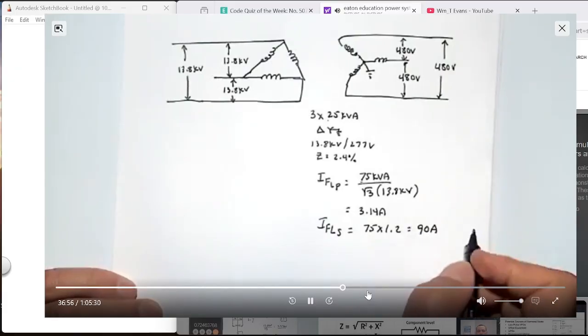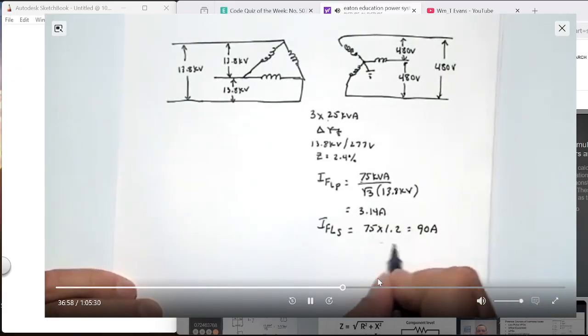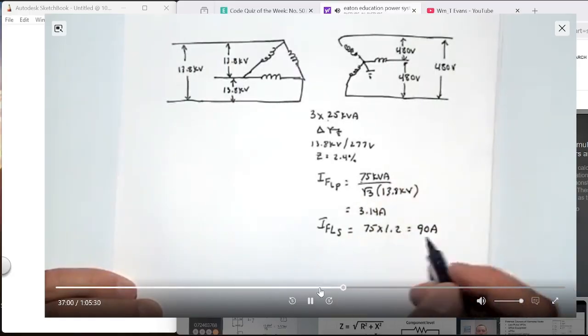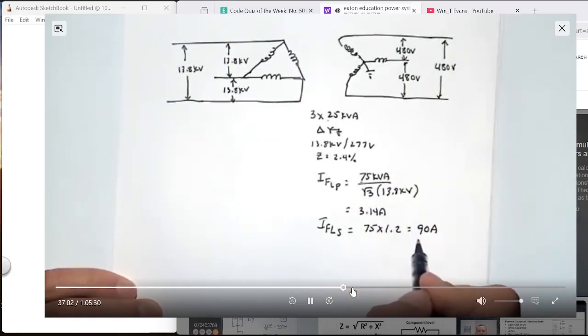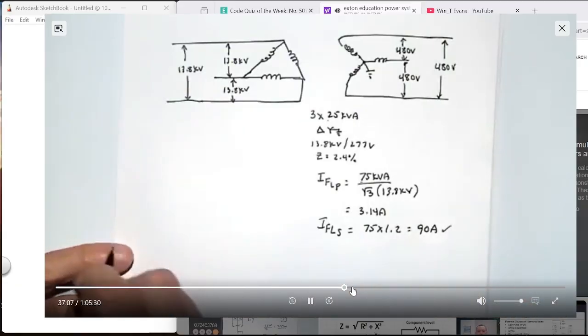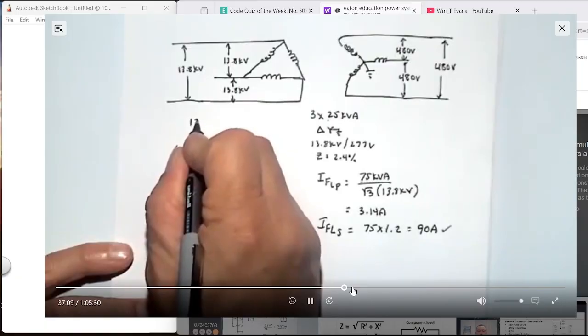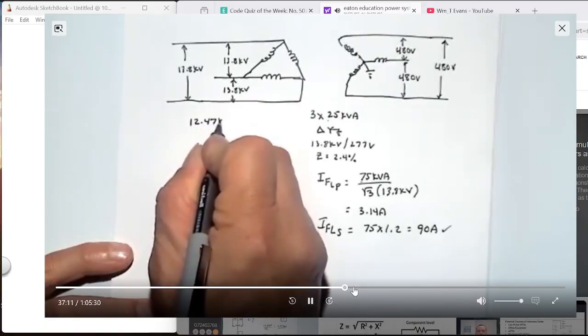So again, we're starting to become more and more comfortable with that. Why is that? Because we're a 480 volt system. Our multiplier on our kVA is about 1.2, so we're at about 90 amps. Okay, now why am I using 13.8 kV? I could use 12.47 kV for medium voltage.